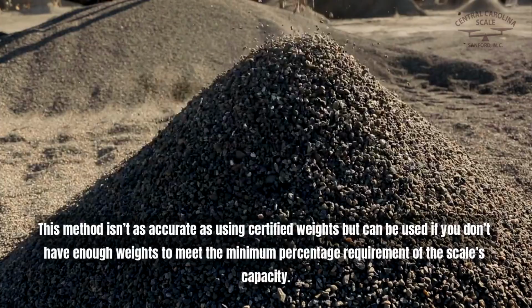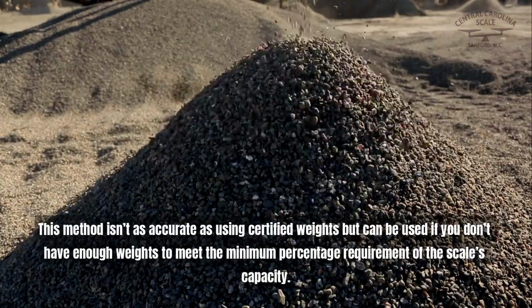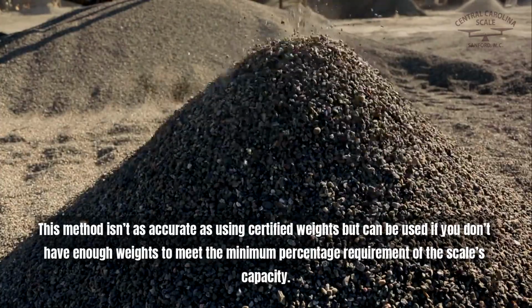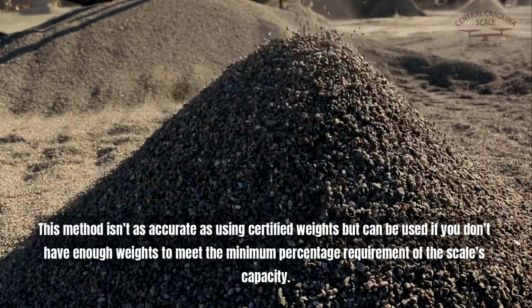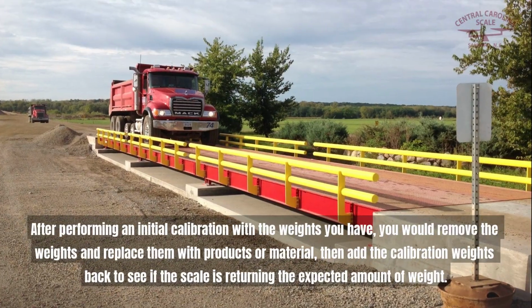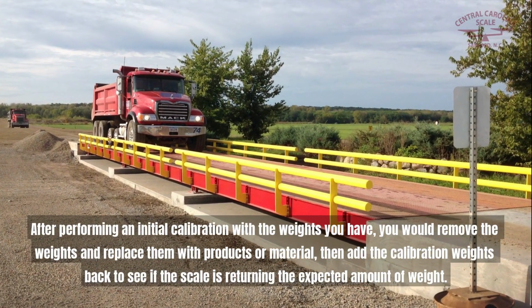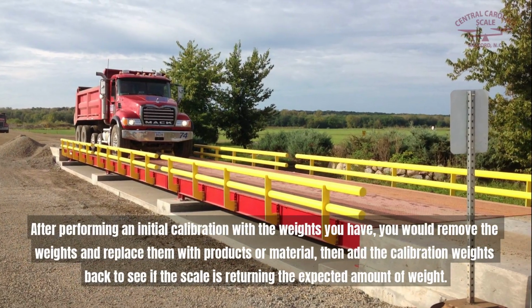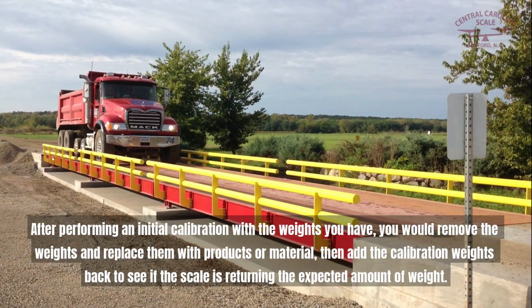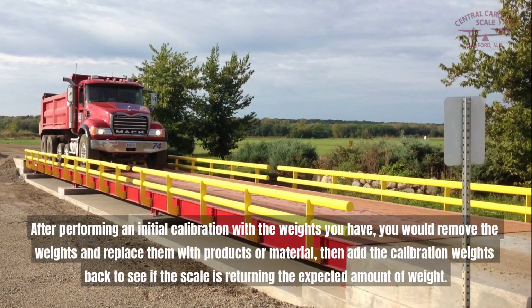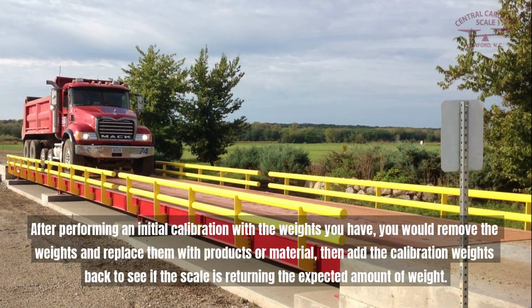This method isn't as accurate as using certified weights, but can be used if you don't have enough weights to meet the minimum percentage requirement of the scale's capacity. After performing an initial calibration with the weights you have, you would remove the weights and replace them with products or material. Then add the calibration weights back to see if the scale is returning the expected amount of weight.